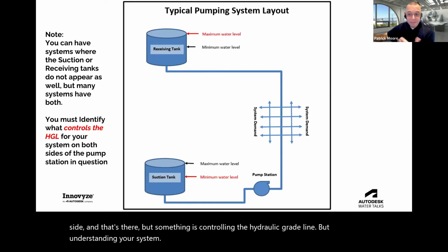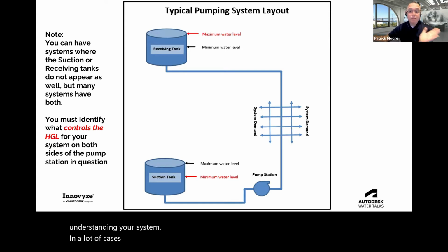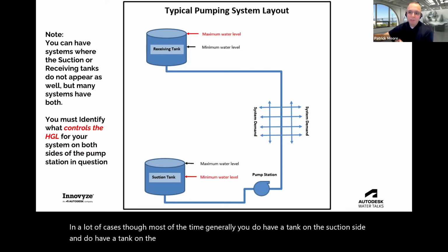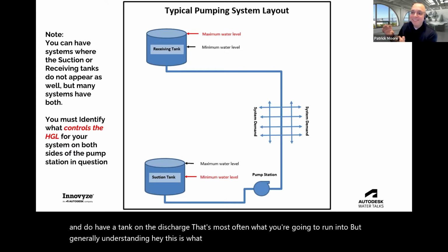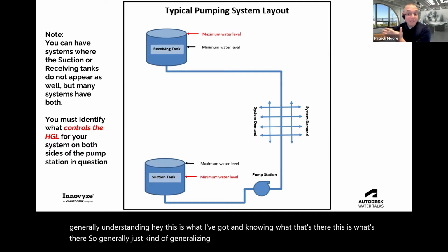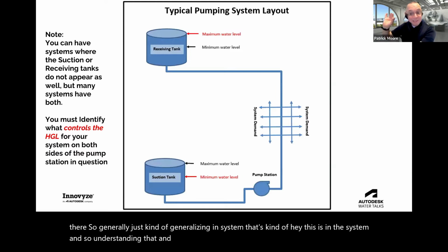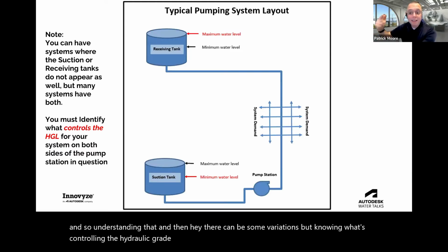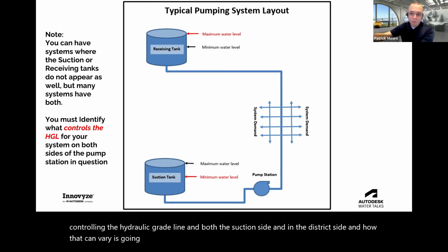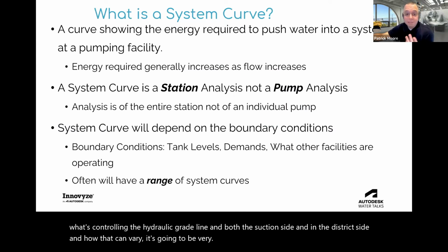In a lot of cases, most of the time, generally, you do have a tank on the suction side and do have a tank on the discharge. That's most often what you're going to run into. But generally, understanding this is what I've got, and knowing what's there. So just generalizing a system, this is my system. There can be some variations, but knowing what's controlling the hydraulic grade line on both the suction side and the discharge side and how that can vary is going to be very, very important. Okay. And so what is a system curve?